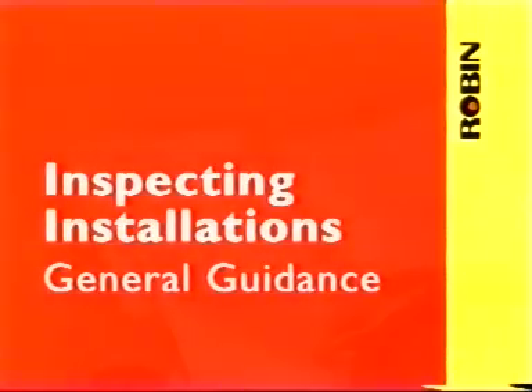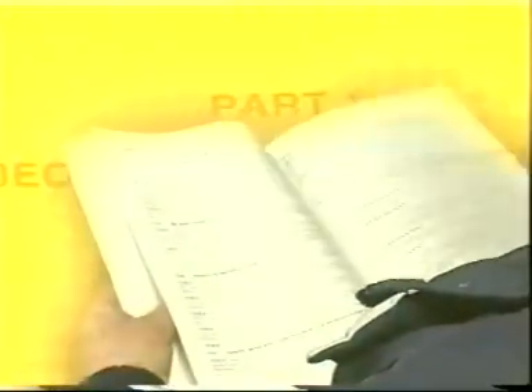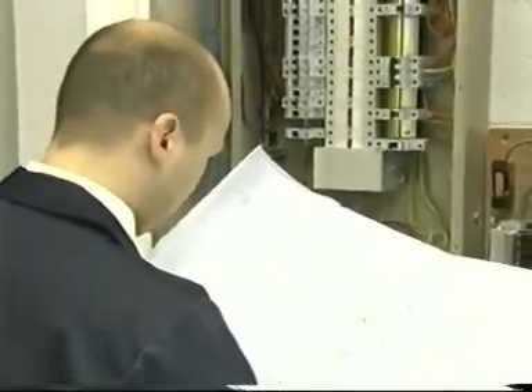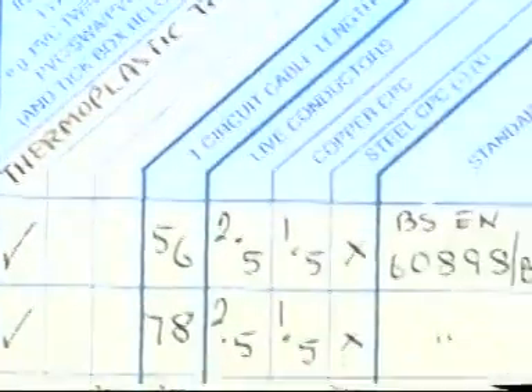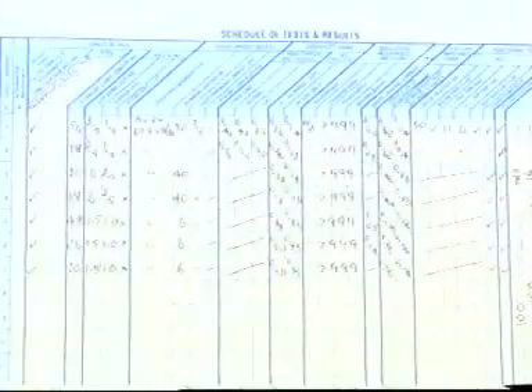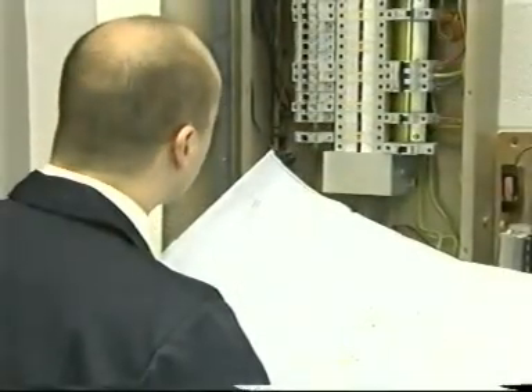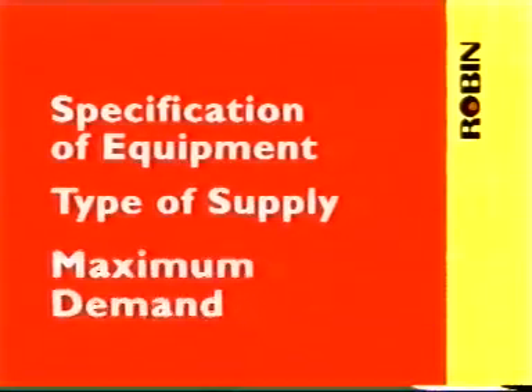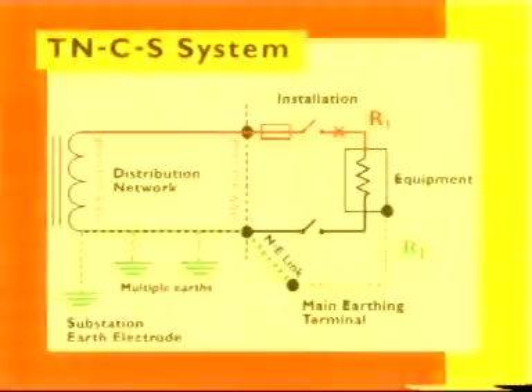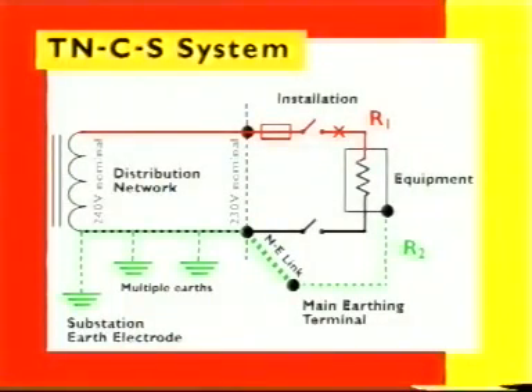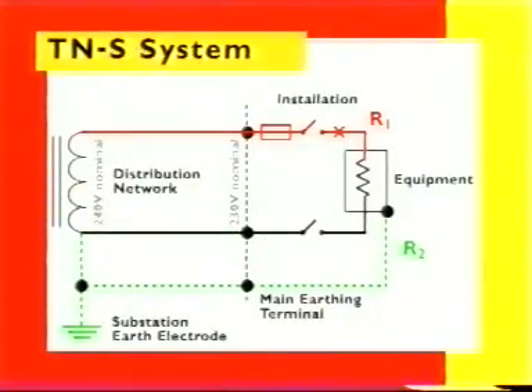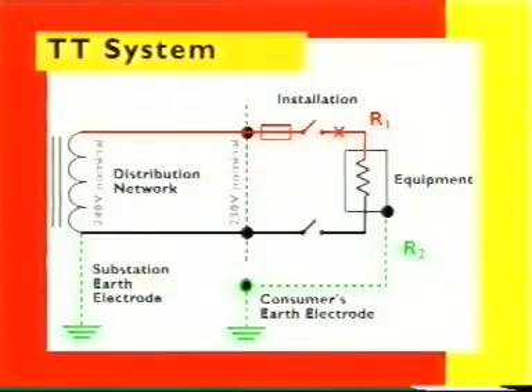A clear understanding of the layout of the regulations is important so that each part can be identified. It's important the verifier has a clear understanding of the installation and how it's been designed and constructed. Past test results are necessary for periodic verification. Information relating to all aspects of the installation must be provided, including specification of equipment, type of supply and maximum demand. Earthing details and installation design data must be available. This information is also required for documentation purposes.